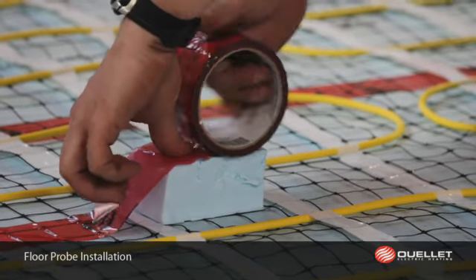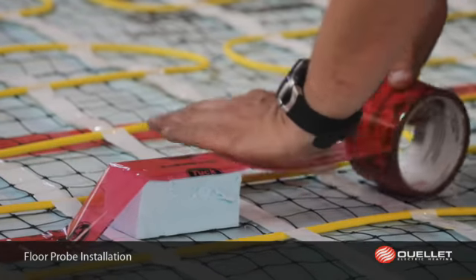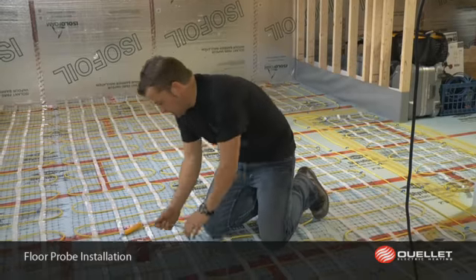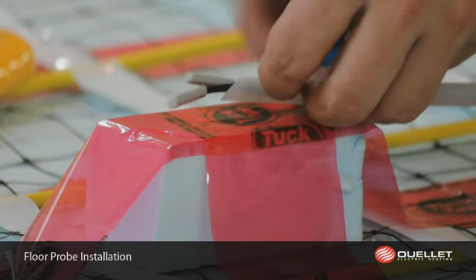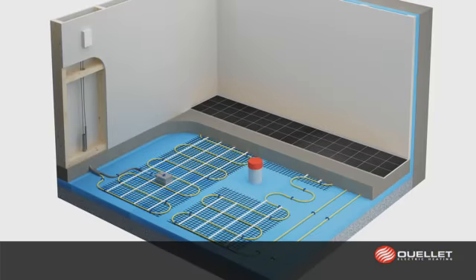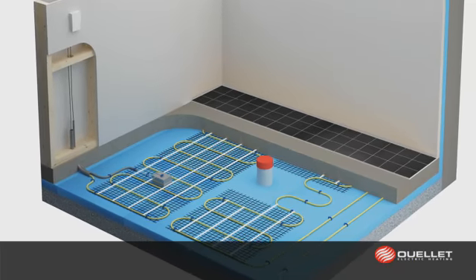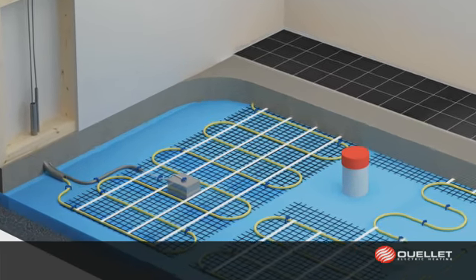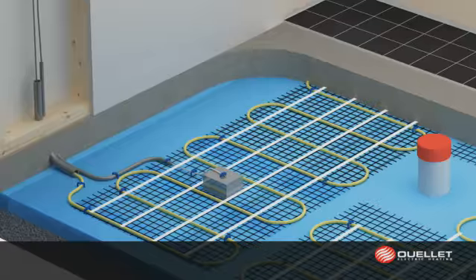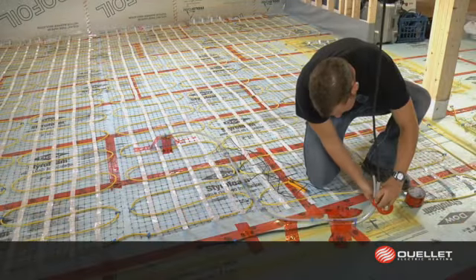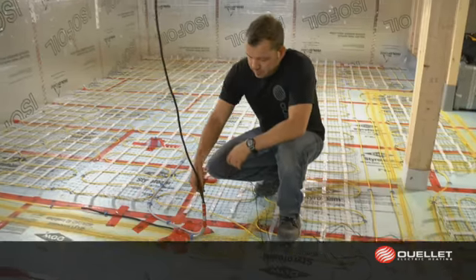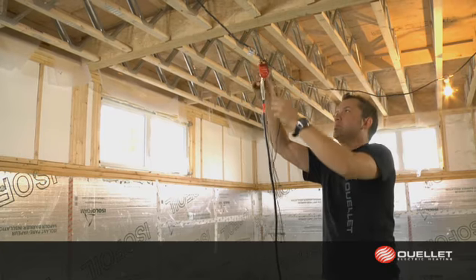In order to protect the floor probe and its wire while pouring the concrete, we suggest inserting it into a conduit. The probe must be installed about 24 inches inside the heated area. The probe must never cross over the cables, but should rather be placed between two parallel cables. Once the mat has been completely installed, unplug the cable check and take the verification measurements again. Record the values on the control sheet.